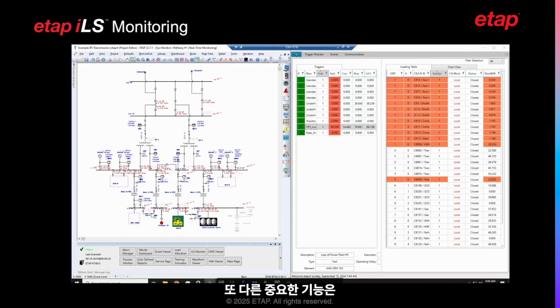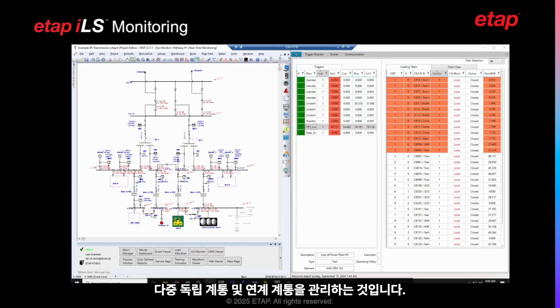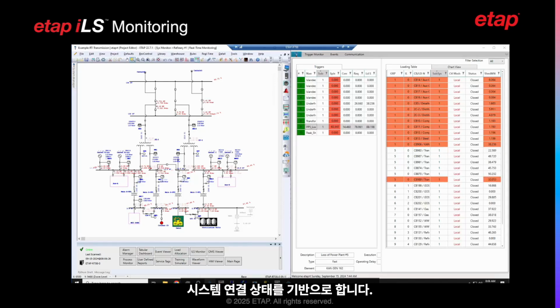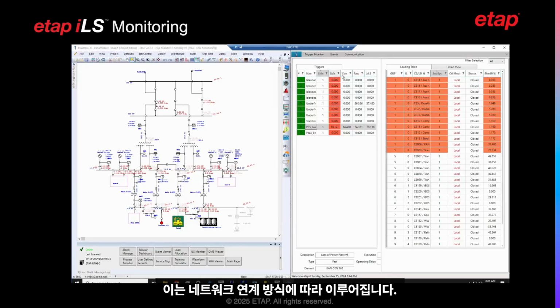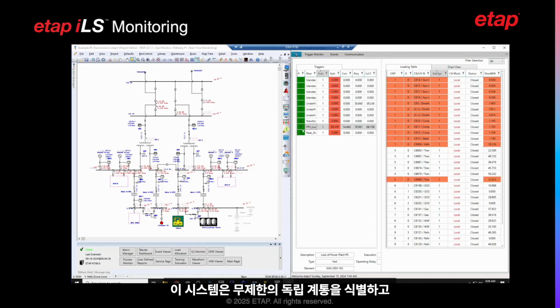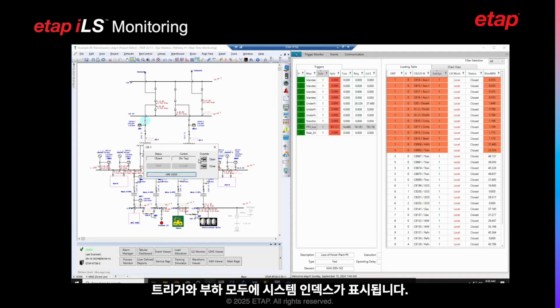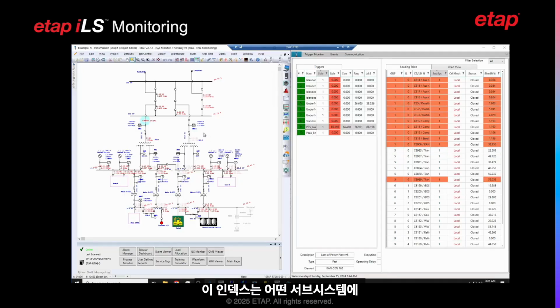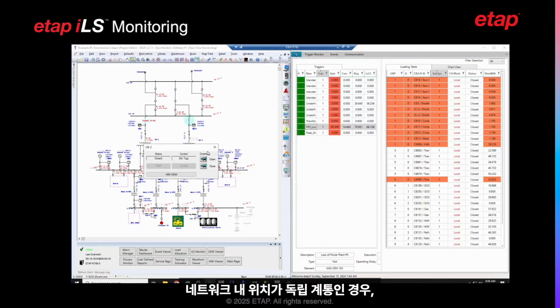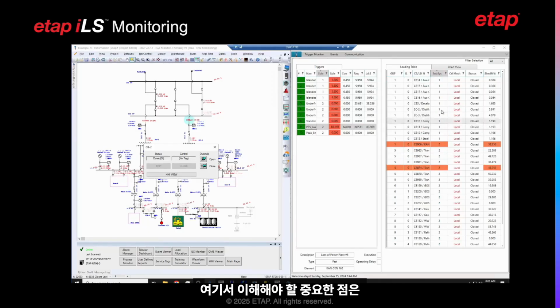Another important capability is the management of multiple islanded and interconnected systems. The ETAP ILS will shed loads based on system connectivity. One of the most powerful features in ILS is the automatic handling of load to shed based on how the network is interconnected. The system can identify an unlimited number of islands and shed loads accordingly. Notice that the ILS trigger monitor shows one system index in both triggers and loads, the subsystems. This index indicates in which subsystem the loads and triggers are located. If the network islands, a new subsystem index is assigned to the new island. It is important to understand that this is done automatically, without the need for any programming. Since it is based on the ETAP model, ETAP ILS understands the topology and performs the assignment of subsystems automatically.